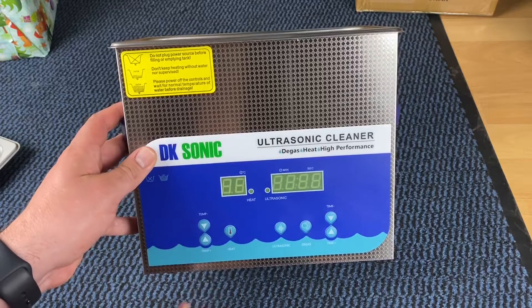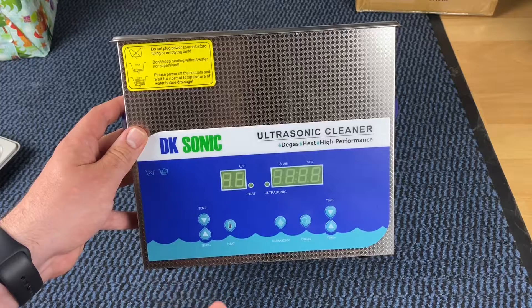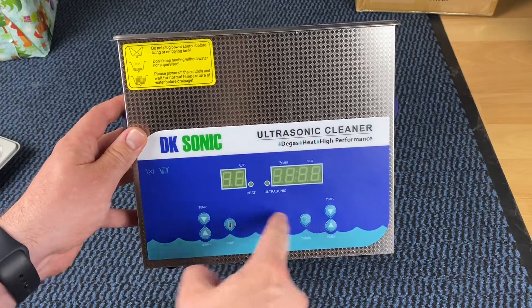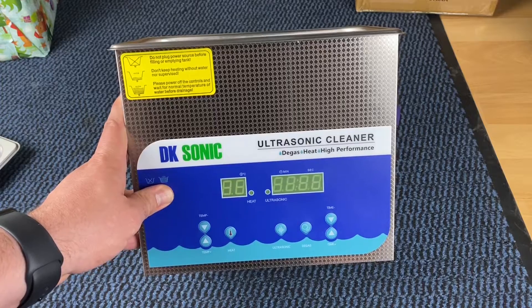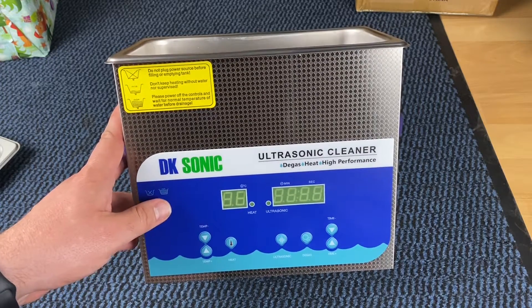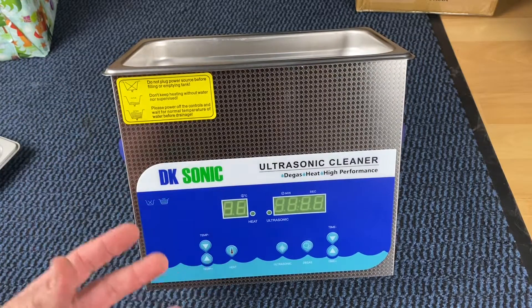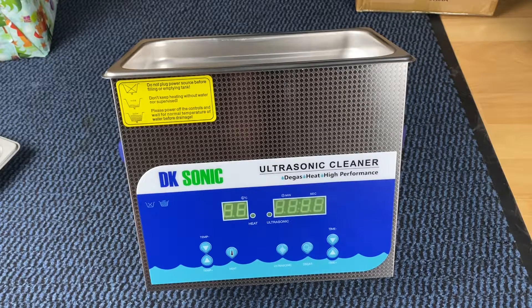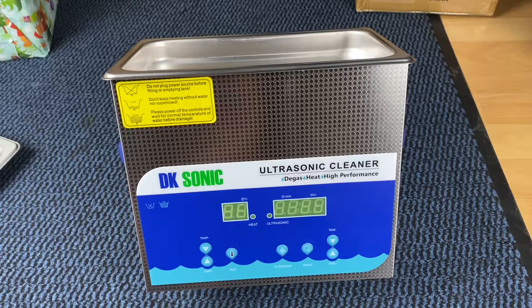Place the cleaner on a flat, clean surface and ensure that the cooling fan will get adequate ventilation and that all controls are set to off. Make sure the drain tap is closed if you have one, and ensure the power lead is securely plugged into the cleaner and that no parts of the lead are likely to contact moisture. Then carefully fill at least one half of the tank with a solvent solution based on cleaning requirements.